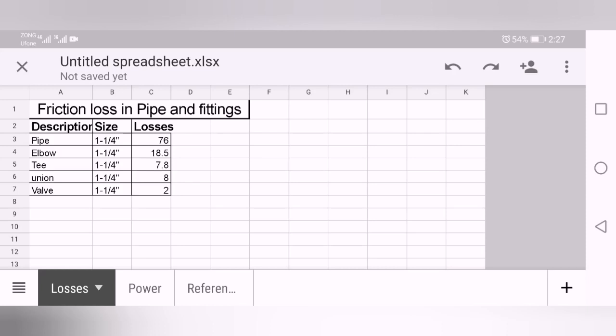This height will be your static height. Second one is the dynamic head. Dynamic head is actually the total losses in your pipes, in your fittings like elbows, tees, valves, unions, and so on. First we will start to calculate the total dynamic head.